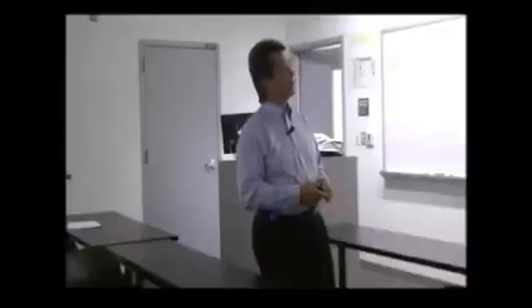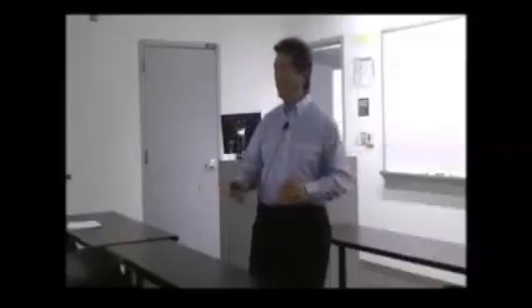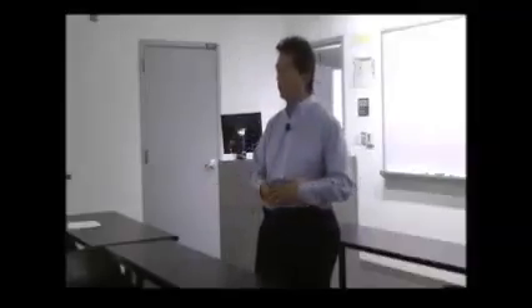Okay. Adjust an overnight purge of facility air. Again, I go back to the economy dampers, economy cycles, being able to use that to purge. In some cases you'll do it purposely to purge that particular building. In some cases you may not, depending on the application. So a movie theater, perhaps after you show the last movie, you may run your cycles and purge that theater for the next 2 hours as you're cleaning and stirring everything up. So you're running the cycles through that. By the time they're done cleaning, it goes back down into your regular cycle, and it's ready for the next day. Okay.